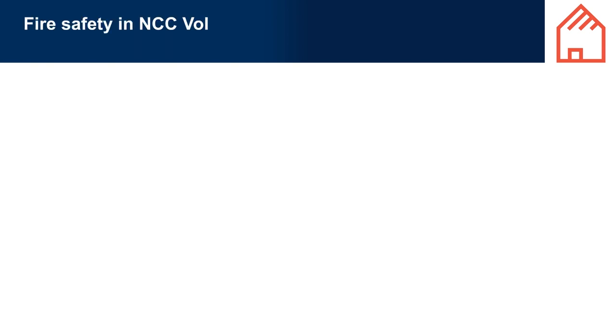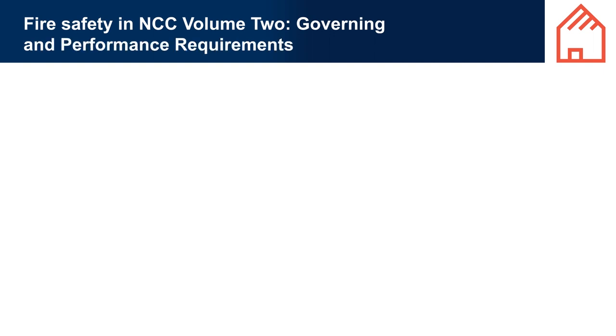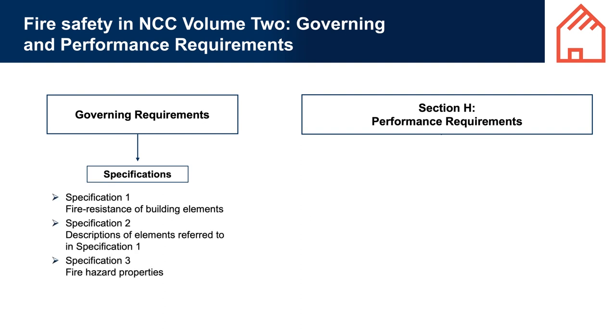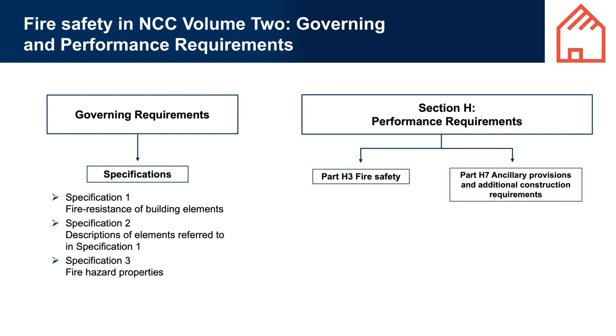Fire safety in NCC Volume 2 - governing and performance requirements. The two performance requirements in Part H3 of NCC Volume 2 reflect the key concerns for fire safety: reducing the risk of a fire spreading between buildings or structures, and warning occupants in the event of a fire so that they can evacuate safely. Protecting the building itself is not actually a primary aim of the NCC fire safety provisions. The building can burn down as long as the occupants can evacuate safely and the fire does not spread to other buildings. The DTS provisions in Part H3 also reflect these key concerns, with particular DTS provisions relating to different factors that affect the spread of fire from or to a building, and one that relates to warnings.